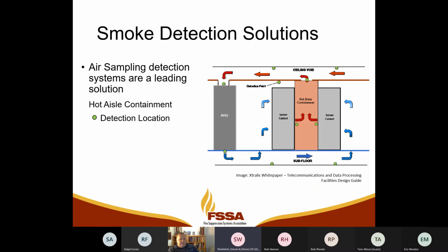So Lee, you mentioned dilution. How do you compensate for the obscuration percentage for activation? Well, air sampling is just one of the technologies that is, two things. It was shown to work through the Fire Protection Research Foundation results, and it's just been shown the telcos, AT&T, Verizon, Sprint, those companies have used air sampling for years, and they never really publish their data, but they catch multiple smoke events, double-digit smoke events, around 50 or so a year using air sampling at return air grills.